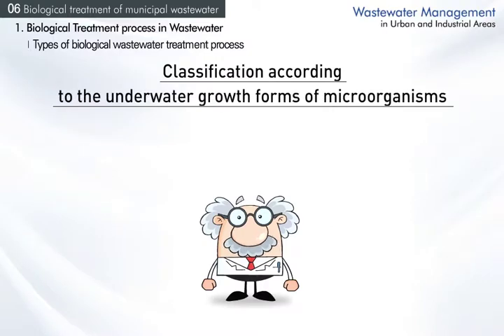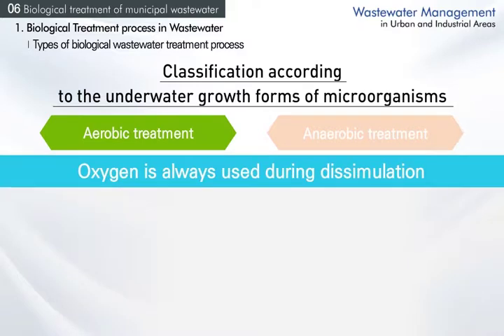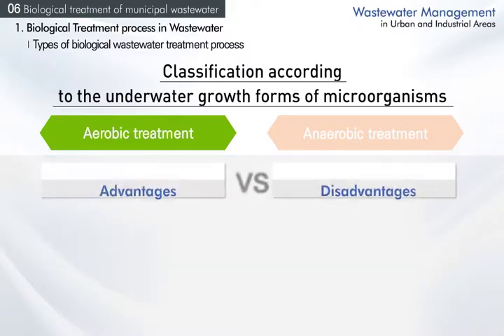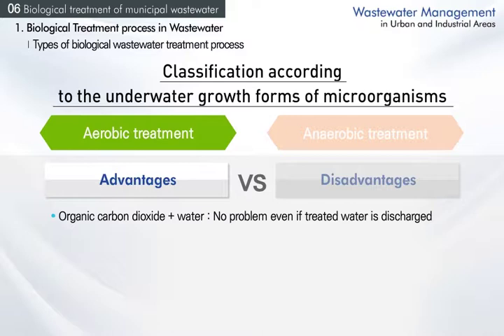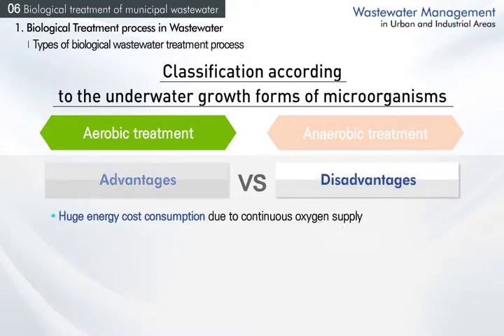The treatment process can also be divided by respiratory characteristics into aerobic and anaerobic treatment. Aerobic treatment uses oxygen for dissimilation to decompose pollutants, including processes like conventional activated sludge, trickling filter, rotating biological contactor, and fluidized bed. Organic pollutants are decomposed into carbon dioxide and water, enabling safe discharge into rivers or lakes. Since aerobic microorganisms grow and remove pollutants very fast, they can treat a huge amount of wastewater quickly. However, oxygen must be continuously supplied, which consumes energy.